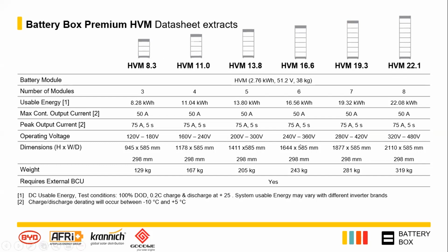So when you're using your high voltage batteries, you always have to keep in mind you have to match your battery bank voltage to your inverter, and it's always best to contact your distributor, Krannich. They can give you advice on how to best integrate your battery and your inverter together.